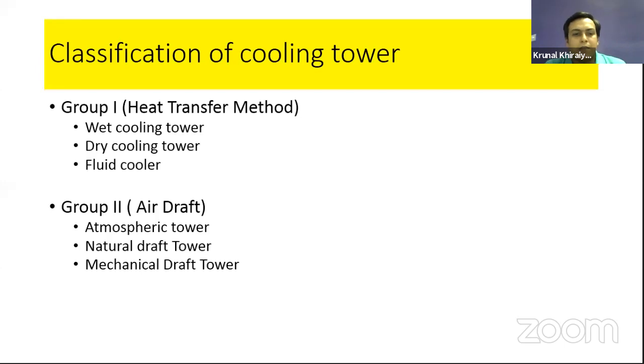The second type is the natural draft cooling tower. In natural draft cooling towers, we generate the draft using different kinds of structures. As we saw in the first slides, there are chimney-type and hyperbolic cooling towers. These kinds of cooling towers come under natural draft towers. Third is mechanical draft. Mechanical draft means we apply some mechanical devices, and due to that, air circulation is generated.